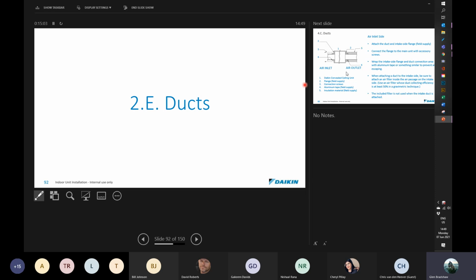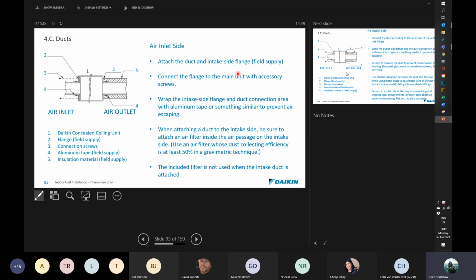Ducts. If we're looking at ducting, what we need to know is that that is the unit at 1. 2 is the flange. You've got a flange on both the return and supply air side. Connection screws go into there. Make sure that these are the correct connection screws. Don't make them too long. You don't want to drill into something inside the unit that you don't want to, like piping and coils and things like that. So use the correct screws.